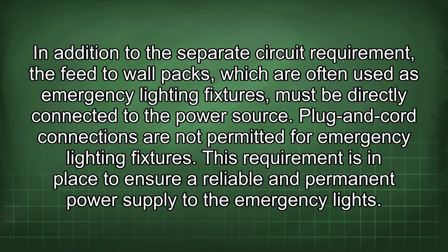In addition to the separate circuit requirement, the feed-to-wall packs, which are often used as emergency lighting fixtures, must be directly connected to the power source. Plug-and-cord connections are not permitted for emergency lighting fixtures. This requirement is in place to ensure a reliable and permanent power supply to the emergency lights.